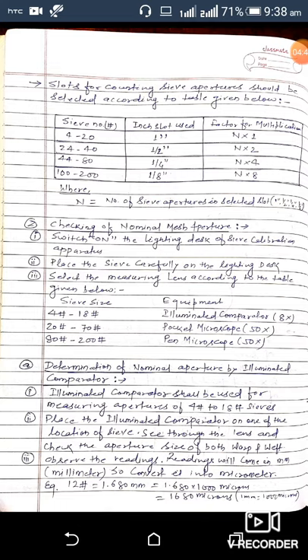Switch on the lighting desk of the sieve calibration apparatus and place the sieve carefully on the lighting desk. Then select the measuring lens according to the table: for sieve 4 mesh to 18 mesh, the illuminated comparator with 8x magnification is used; for 20 mesh to 70 mesh, the pocket microscope with 50x magnification is used; and for 80 to 200 mesh, the pen microscope with 50x magnification is used.